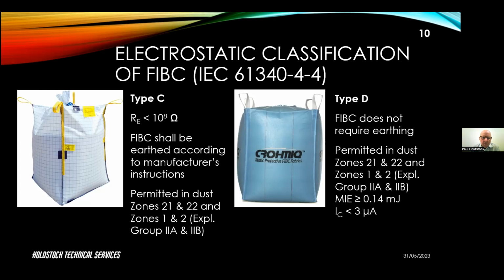And with the FIBC earthed, they are safe for use in both the dust zones 21 and 22, and where you might have explosible gases or vapors, so in zone 1 and zone 2, in the explosion groups 2A and 2B. So not for the most sensitive gases like hydrogen, but then you're unlikely to be using an FIBC in those zones anyway. And then there's also the type D.